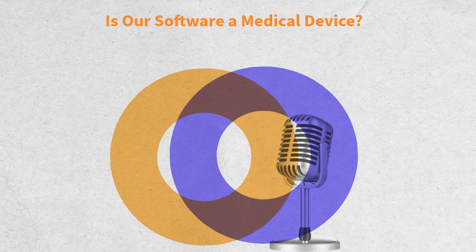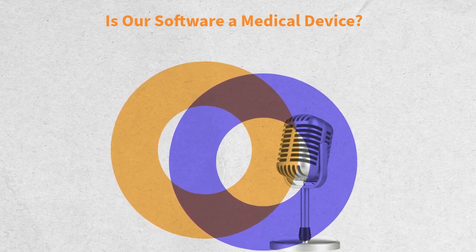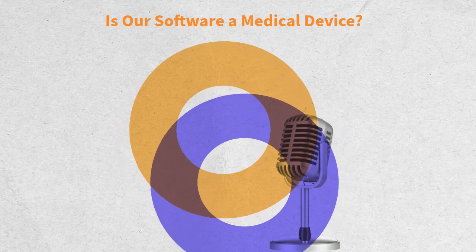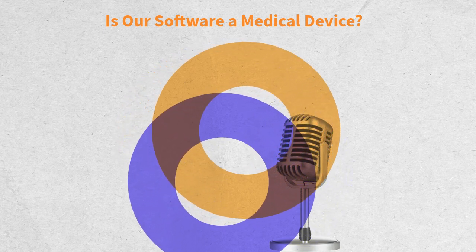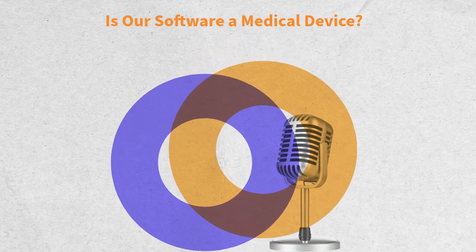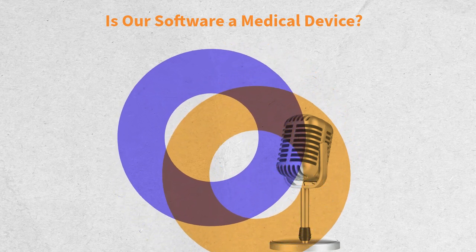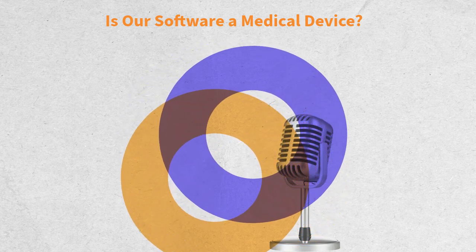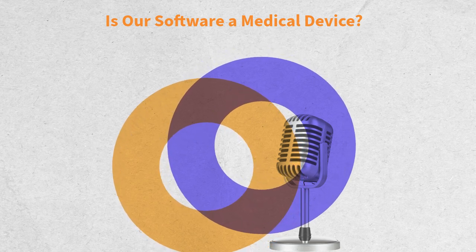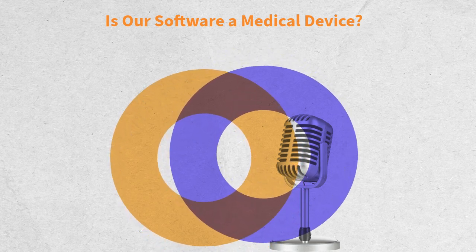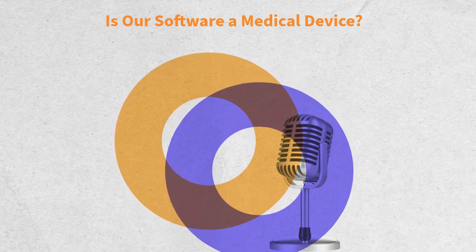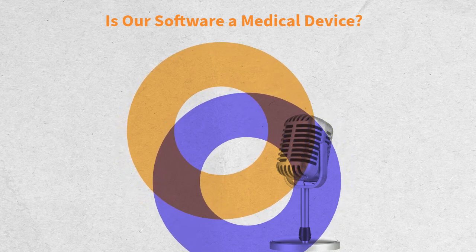Should a software processing clinical data be CE marked? This also depends on the scope. If the processing has a clinical purpose, for instance, it points out out-of-range values, supports diagnosis, sends alerts, then yes, the CE marking is required. If, on the other hand, it collects or displays data with no direct scopes of diagnosis or alert, it might not be required.